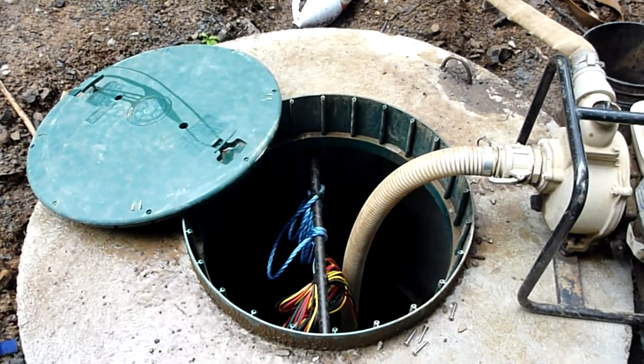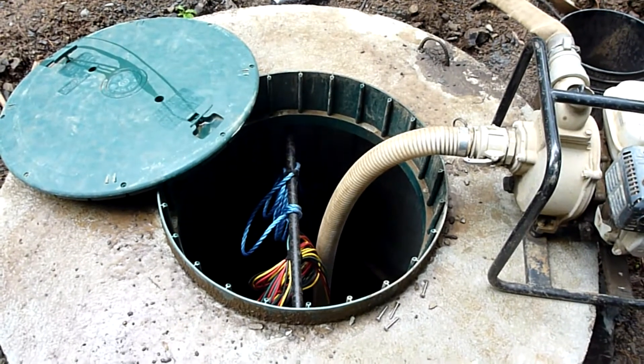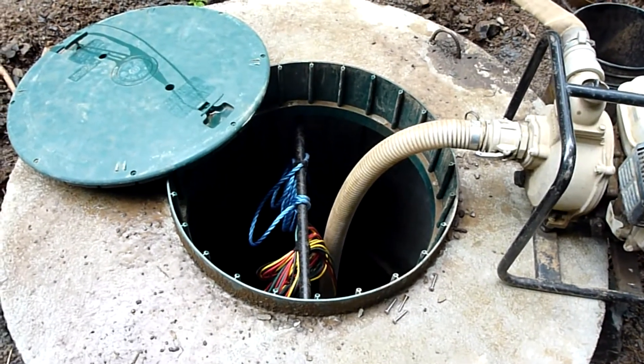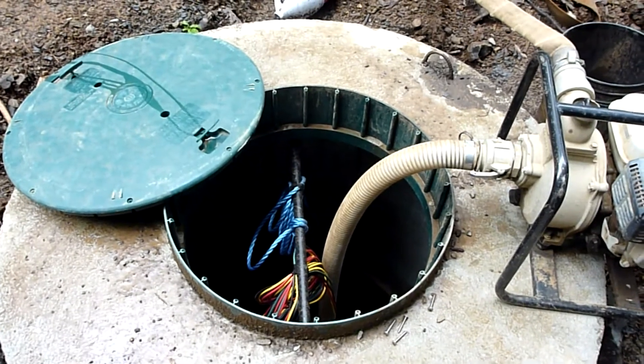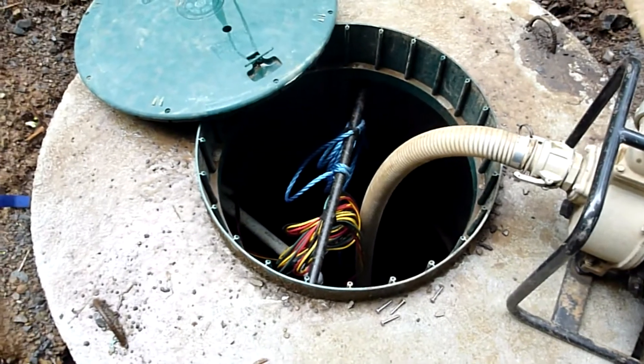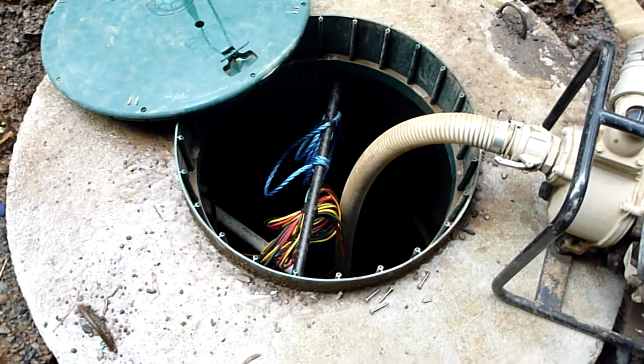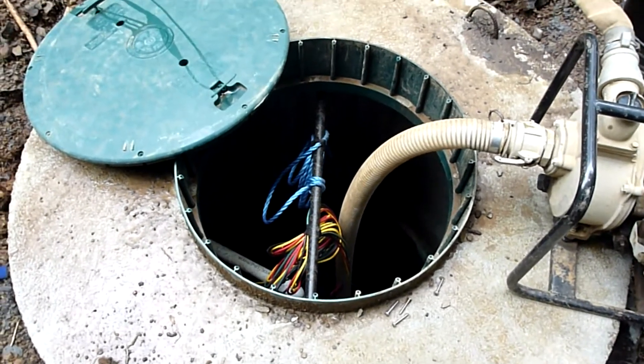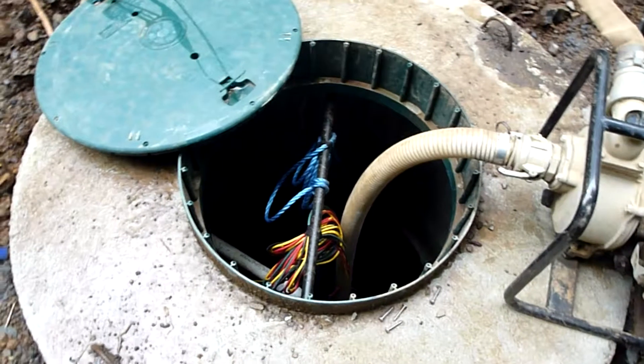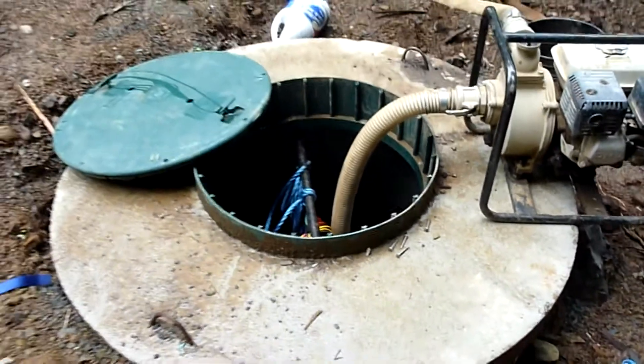After that, we'll pump her dry after letting it sit for a couple of days, let her fill back up naturally, and I might pump her out one more time just to make sure we flush out all the chlorine so we don't get a false reading when we send the water sample off to the lab. The idea is we want to get an accurate sample of what the water is coming into the well, see whether we need any treatment for potable water. After that, we'll send another sample off to the lab to check out our water quality and see if we need to do anything for softening the water.